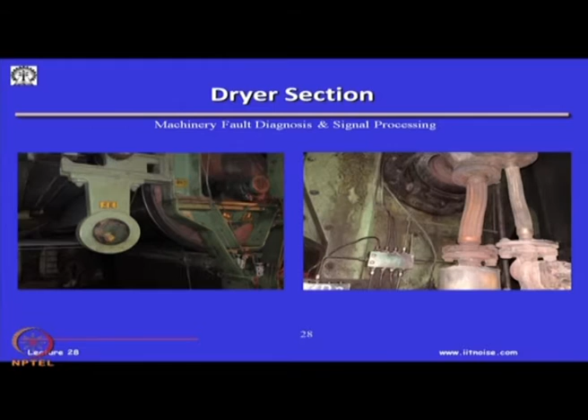There is a bearing here, the bearing here, and you will see in such a plant, the bearings are monitored by vibration. You will see these white lines here. This is a bearing transducer here, another bearing transducer here, another bearing transducer here. So, round the clock vibration monitoring of these rolling bearings is being done, and then there are diagnostic algorithms wherein people can know which vibration signal is coming from which bearing, what is its kurtosis value, what is its spectrum value. Okay. And these are very critical operations, because imagine if one roll breaks and falls, it is going to damage a few other rolls, it is going to damage a few other bearings, and to put everything together, you can imagine the problem one has to face.